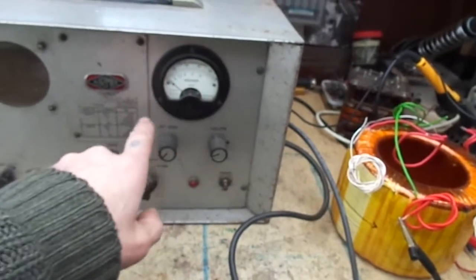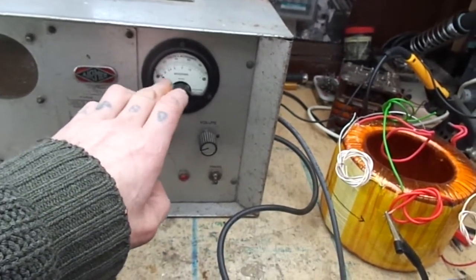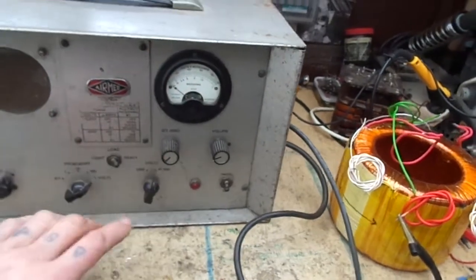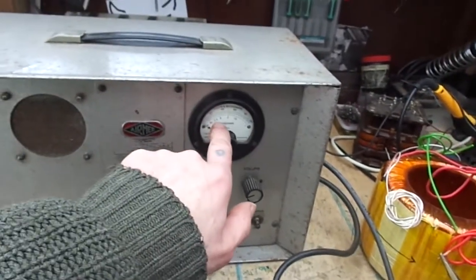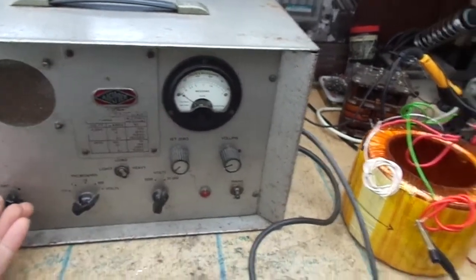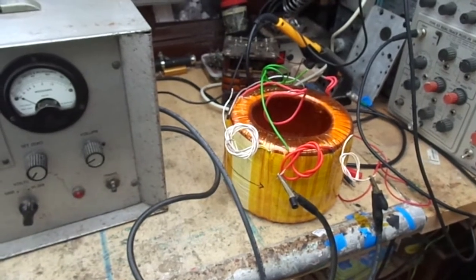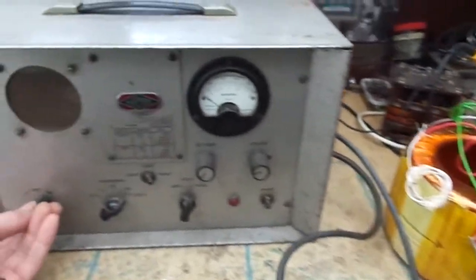We're testing the primary-secondary insulation on this big toroid. I tested it up to a thousand volts, tested the insulation, and it works out at about 500 megohms. I think I've got that right. Basically read 5 off here, times it by 100.